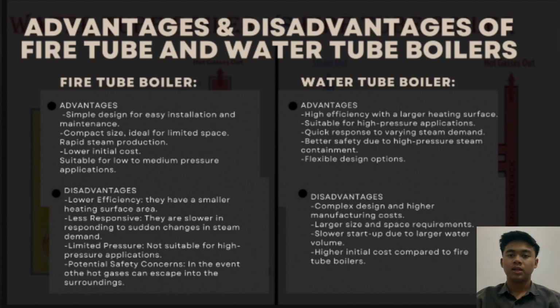So the disadvantages of fire tube boilers. Lower efficiency: fire tube boilers are generally less efficient because they have a smaller heating surface area. Less responsive: they are slower in responding to sudden changes in steam demand. Limited pressure: not suitable for high pressure applications such as power generation. Safety concern: in the event of a rupture, the hot gas can escape into the surroundings.